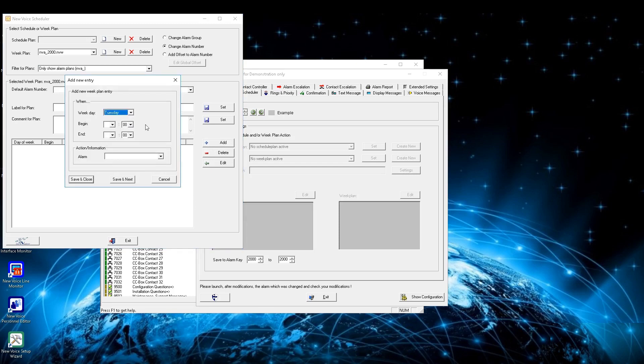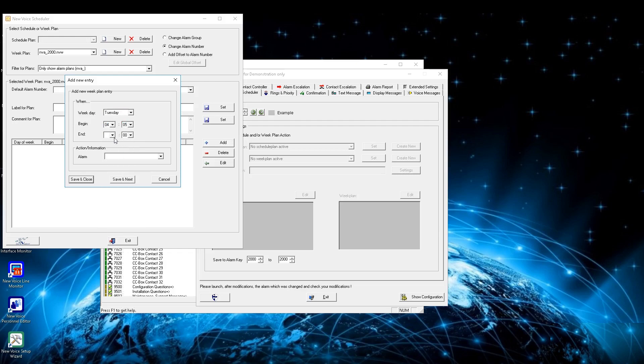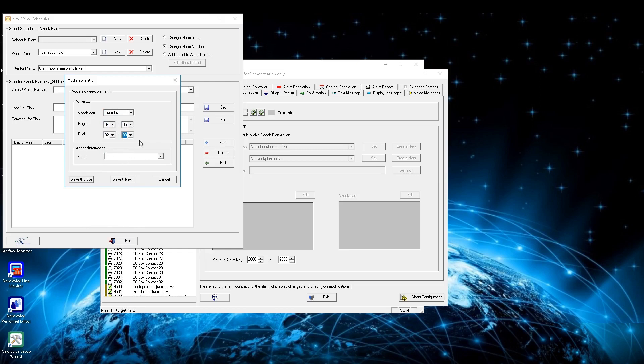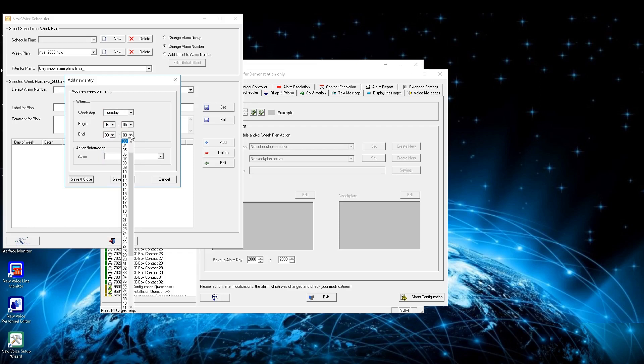Warning: when using the week plan editor you can't jump over 12 o'clock AM. You can either go on one day to 23:59 and on the next day from 0 o'clock to the wanted time. For example with day and night shifts, we recommend making the default group or default alarm the night shift and just switching to the day shift group in the defined time from the scheduler. Press save and close to confirm your settings, or save and next to define more entries.